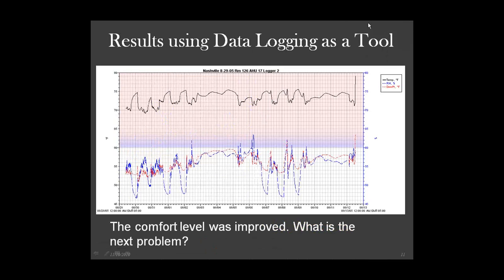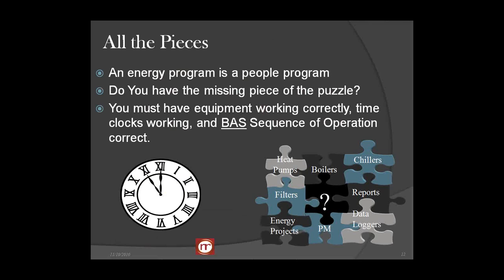Now, after we went into the building, we checked everything. And I'll show you some of the things that we did in a minute. But look at the space temperature, basically the same in the black, but look at the humidity levels. Here's my alarm level at 60%. Now you can only see a few spikes that would have triggered the boiler for very short periods of time rather than the entire time. And notice where our humidity's camped out. We're in that 50 to 55% range most of the time. So this was a successful campaign in this building. It took about 2 months to achieve.